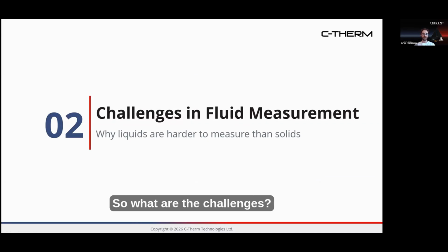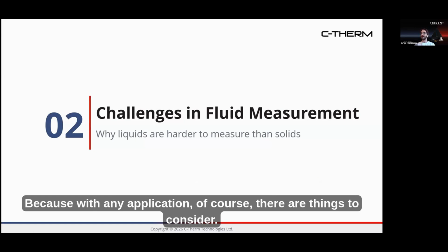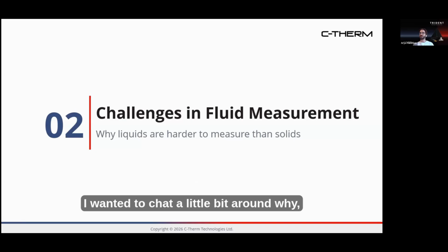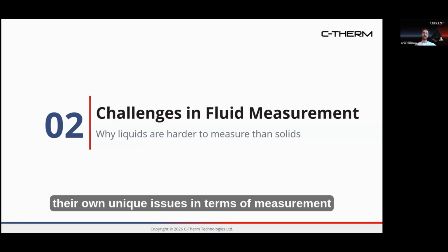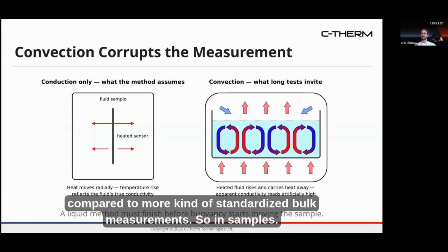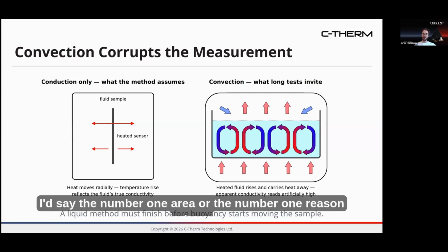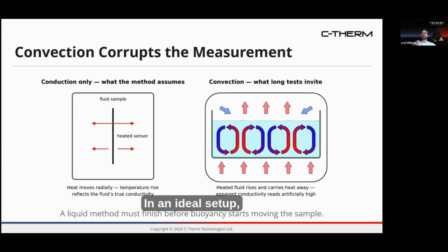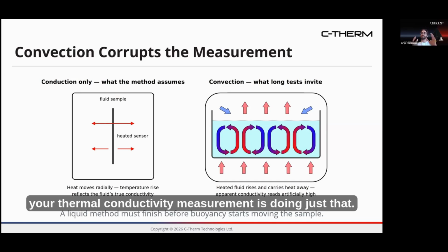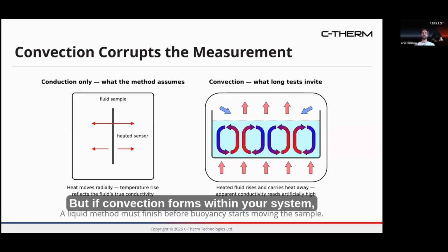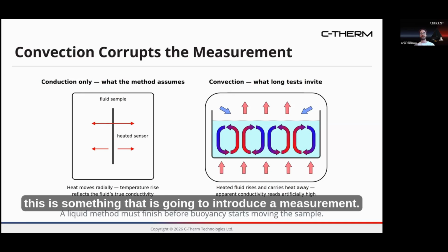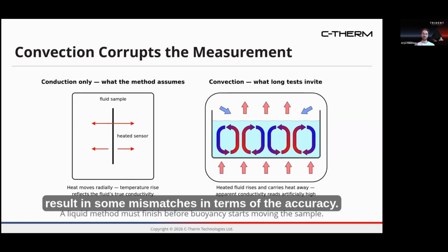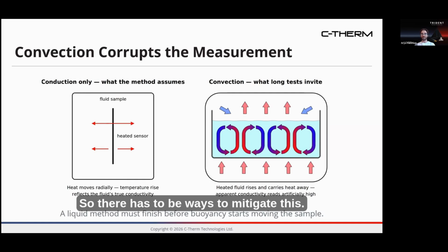So what are the challenges? Because with any application, of course, there are things to consider. And from the thermal side of things, I wanted to chat a little bit about why, in some cases, liquids introduce their own unique issues in terms of measurement compared to more standardized bulk solid samples. And I'd say the number one reason where liquids data goes wrong is when you get convection. In an ideal setup, your thermal conductivity measurement is doing just that. It's measuring thermal conductivity. But if convection forms within your system, this is going to introduce a measurement bias. Any form of heat transfer, not solely through conduction, will result in some mismatches in terms of accuracy. So there have to be ways to mitigate this.